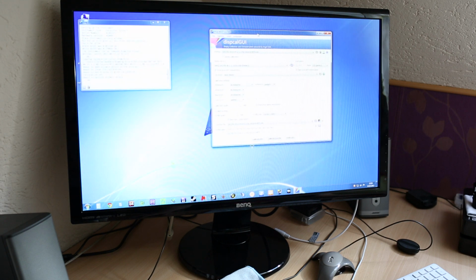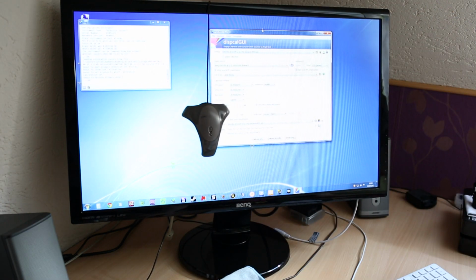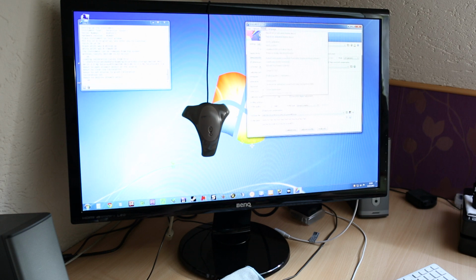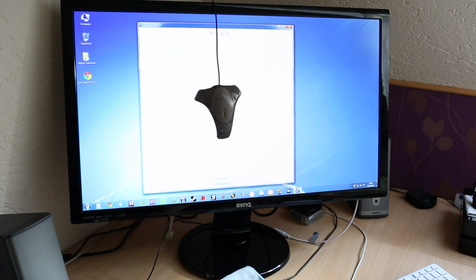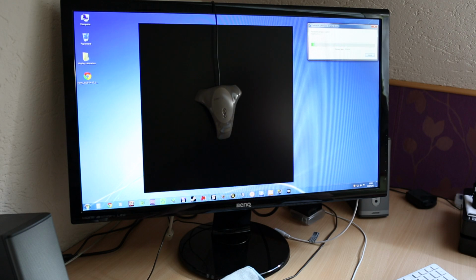So if you like to measure your contrast ratio, I'm going to show you another tool set that you get with dispcalGUI. Under tools you have report and calibrate display device, and you just put this one somewhere right in the middle. Start measurement. It's going to do 4 measurements, I think, or 3. Yeah, you get a black, white, and a gray. That's not going to take long. Hope the battery on the camera still does its job. Alright. White, and okay, another black. I think it's still using the black and white measurements for the compensations, which is okay, doesn't matter that much.